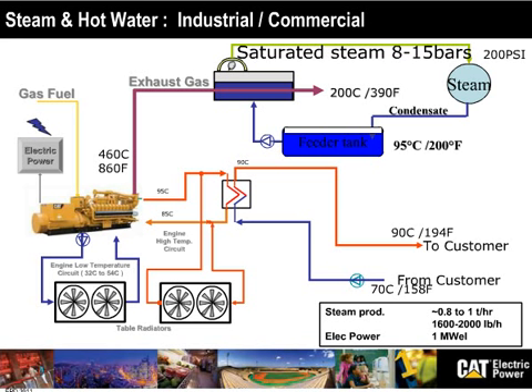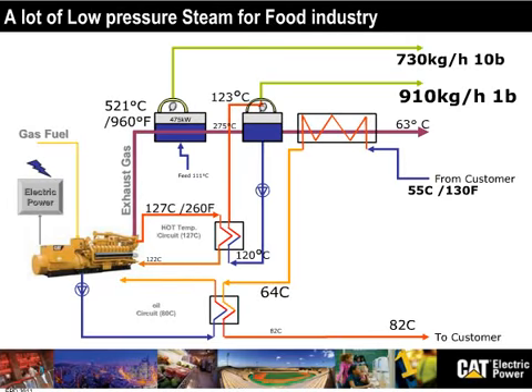For instance, in food industry, there is need for steam at low pressure. And here, using our hot ebullient cooling Caterpillar genset, running with the jacket water temperature at 260 F, 127 C, we are capable to produce 700 kilograms per hour at 10 bar steam, and also 910 kilograms per hour of steam at 1 bar. So total of steam is now 1.6 ton instead of 1 ton.